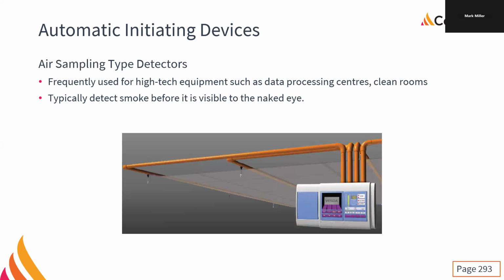These things are really, really sensitive, and we can detect the smoke from very, very specific locations because they are air sampling. They have a fan built into them. They are sucking air from whatever environment they need to and running it through the smoke detector mechanism inside the units. These can be used in place of open area detection. Like we can put a giant piping system in and use it to protect the open areas. Not common because these things are very expensive. We typically use them in very, very specialized applications, mostly data processing centers, the data centers.